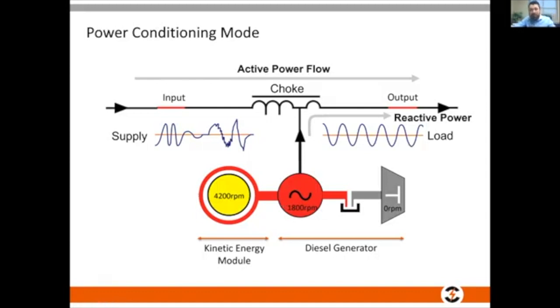And it will do that for 5, it will do that for 10 seconds. I only need to do it for 5 seconds because at such time the engine is now at 1800 RPM and it is nothing more than a diesel generator. Once that engine is driving this machine, it is nothing more than a diesel generator. All the flywheel is doing is providing 5 seconds of energy transfer. It's providing that bridge, that gap from utility failure until the engine can become the prime mover.